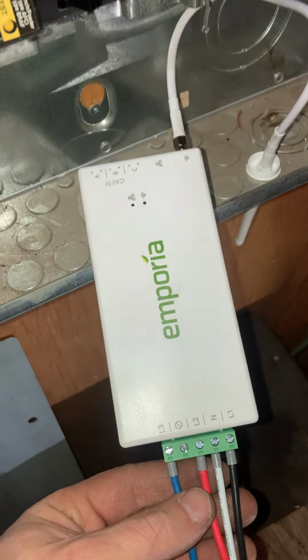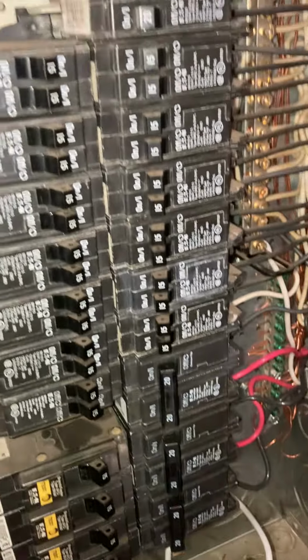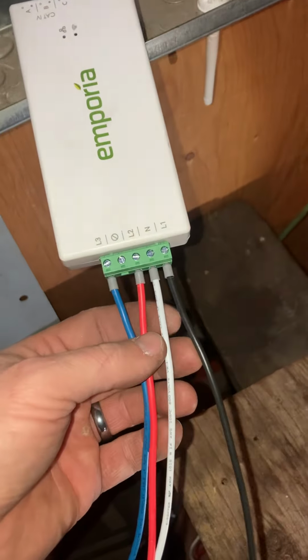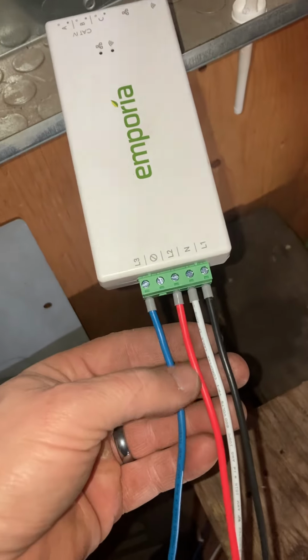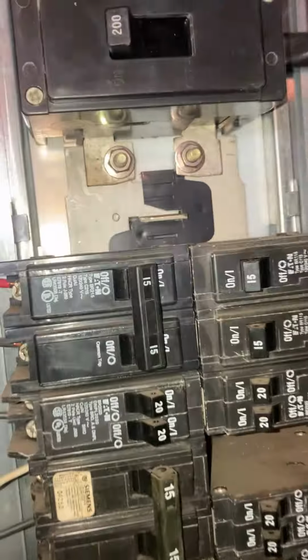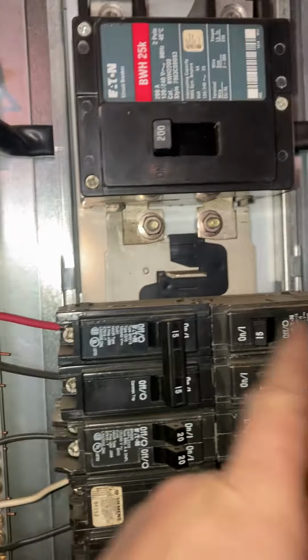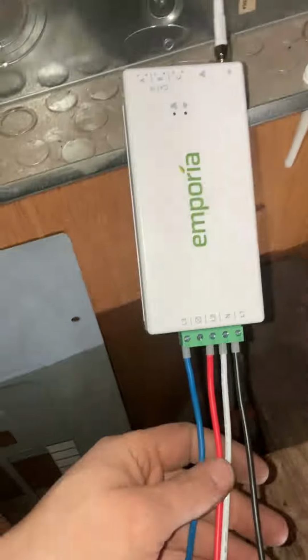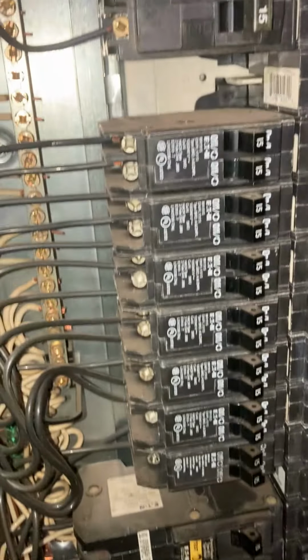So we're going to pick up some power from one of these outlets, and the other ones are going to go, one to the neutral, and two to each phase of your 120s on here on either side, and the other one's going to go to the neutral bus bar. So I've got my wire fished in behind here, and this is where you want to be careful.